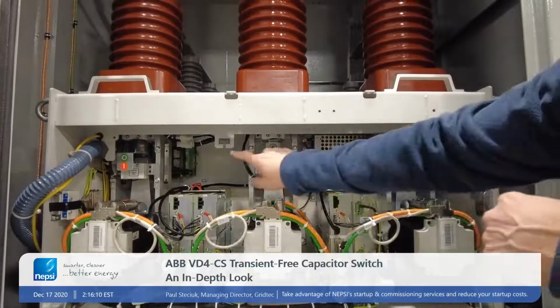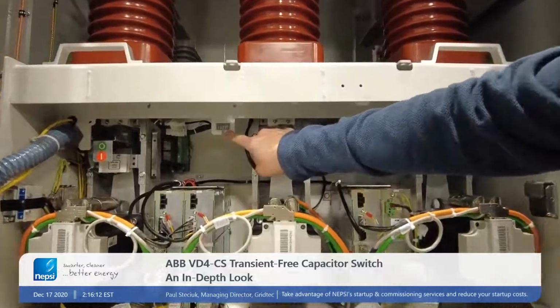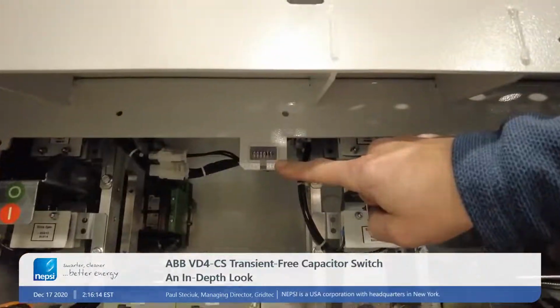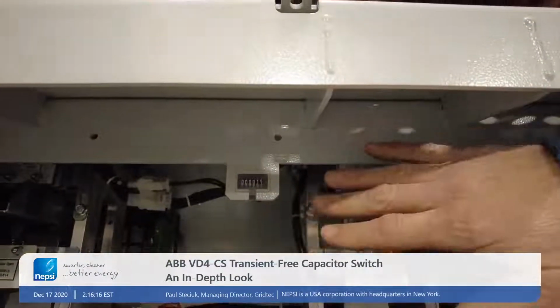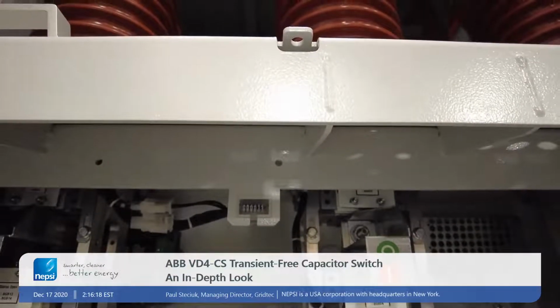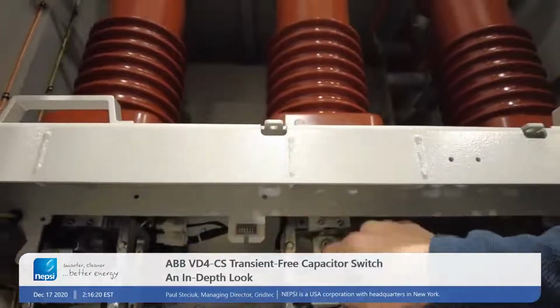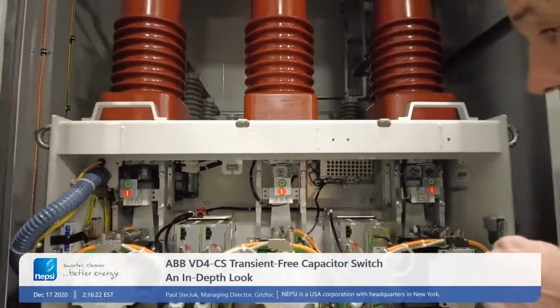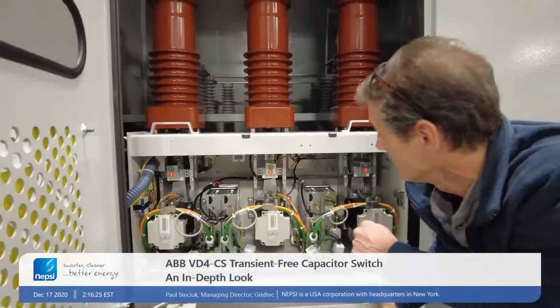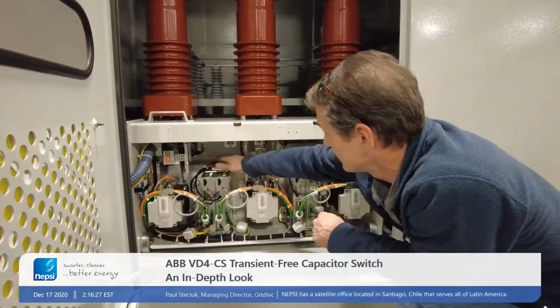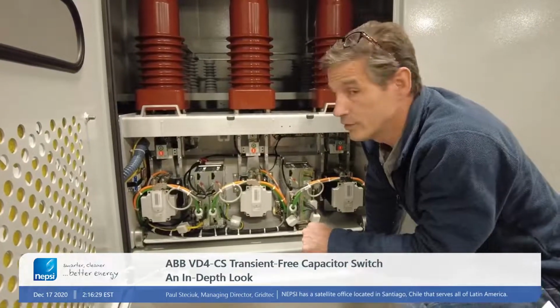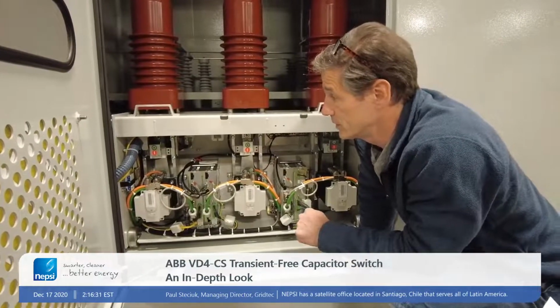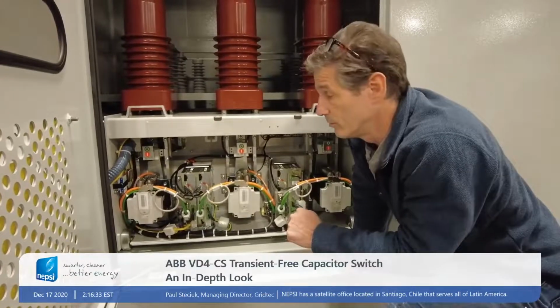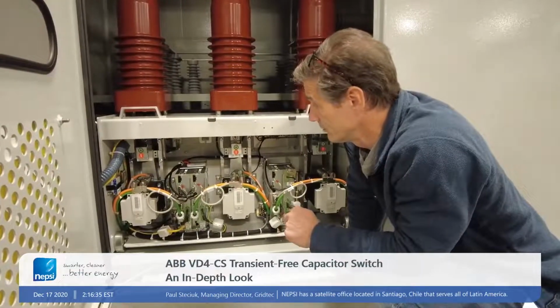So one of the things, when you zoom in down here, you can also see there's an operations counter that gives you the number of counts. You can see that even when the cover is on the breaker. There's a capacitor in the back here that has stored energy, so if there's a loss of voltage, there's enough energy to trip the breaker in that scenario.